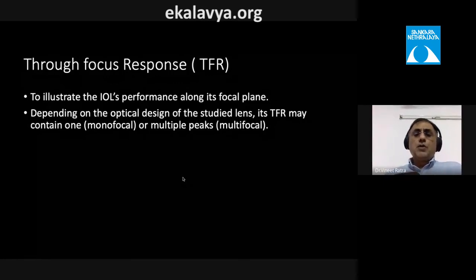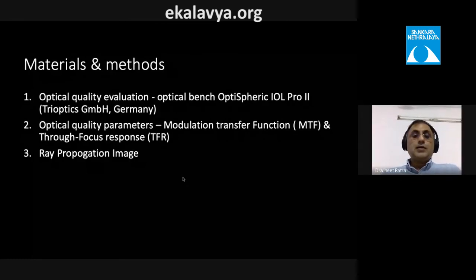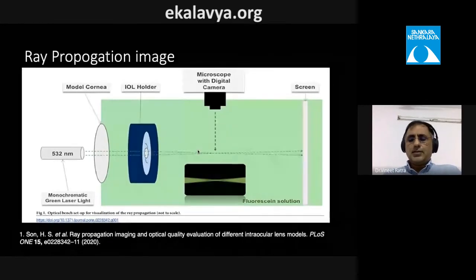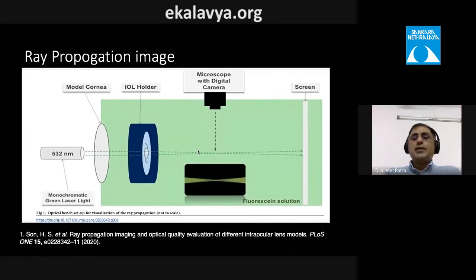The through-focus response (TFR) illustrates IOL performance along its focal plane, showing one, two, or three peaks for monofocal, bifocal, or trifocal lenses. Ray propagation imaging uses fluorescein solution with the lens in a holder, a model cornea, and monochromatic green light to visualize the focal distribution — useful to confirm whether a lens is truly unifocal or has multiple foci.